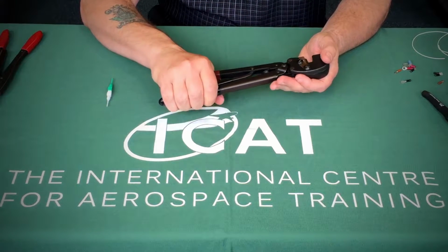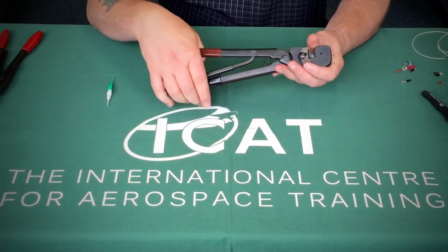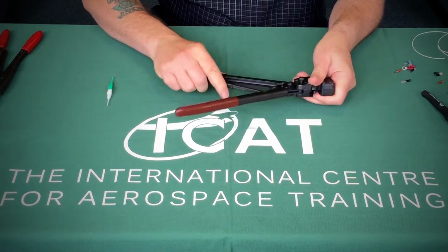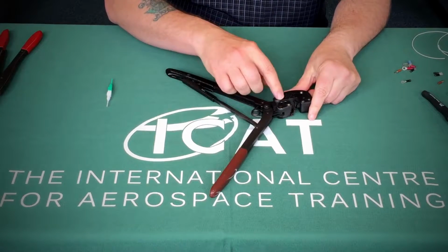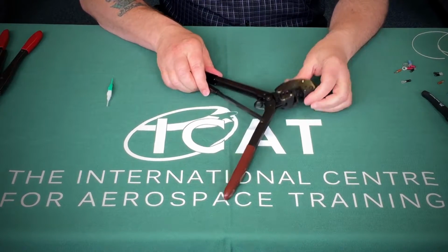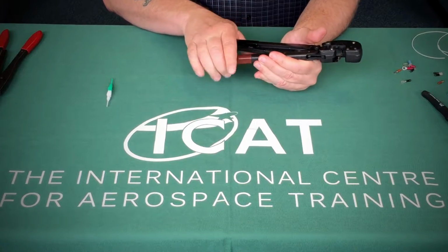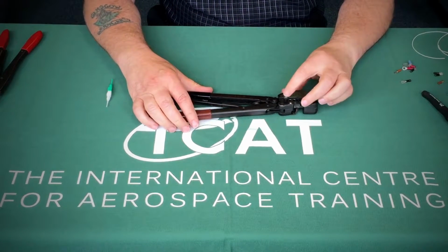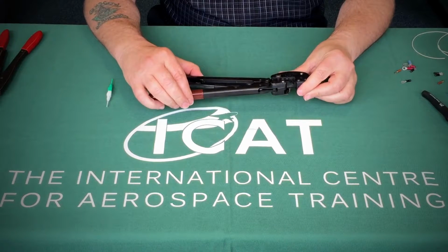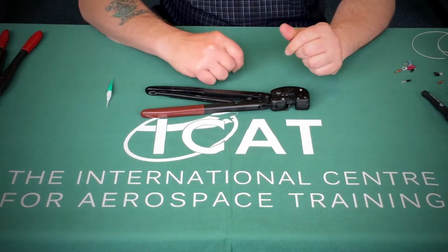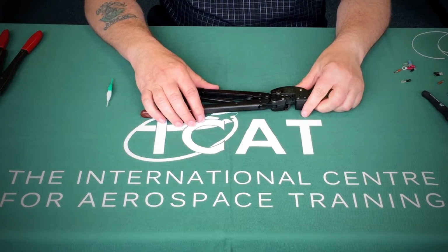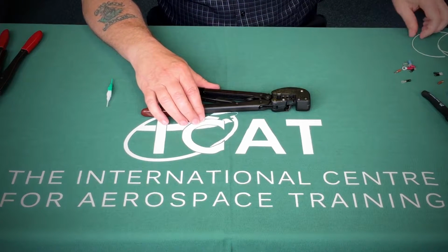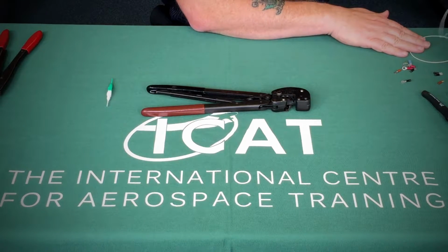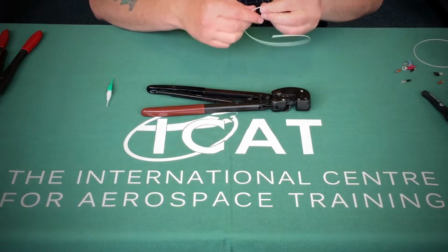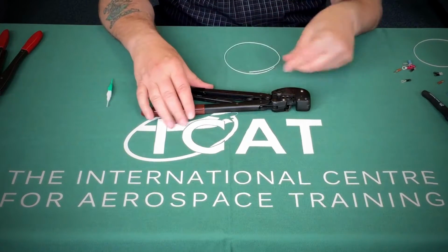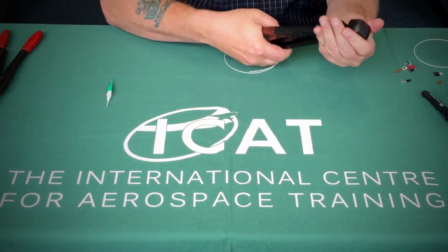Okay, we're now going to start. Prior to use, some of the checks that we may want to do is to check that the insulation pin is in the correct position. Remember, I said earlier, it should provide support on the crimp to the insulation itself. Now, one method they recommend that you test this insulation crimp position is to actually crimp a connector onto a piece of unstripped cable, as we can see here. It's a fairly straightforward method.